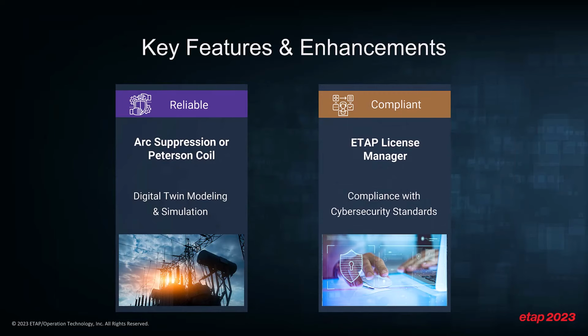Peterson coil, ground fault neutralizer, or arc suppression coil. No matter where you are in the world, you know this device as an iron core reactor that's connected between the transformer neutral and the ground. And it's used for limiting the capacitive earth fault current, which is flowing at the time you have a line to ground fault. It also reduces the transient fault, which occurs due to lightning, and also helps minimize the single line to ground voltage drops. ETAP 2023 now includes the ability to model arc suppression coils or Peterson coils as part of the fault analysis studies, and also includes in effect in other analysis such as protection and arc flash studies.